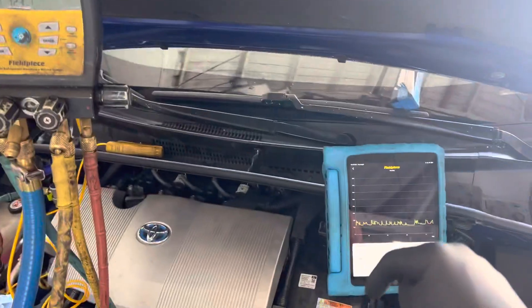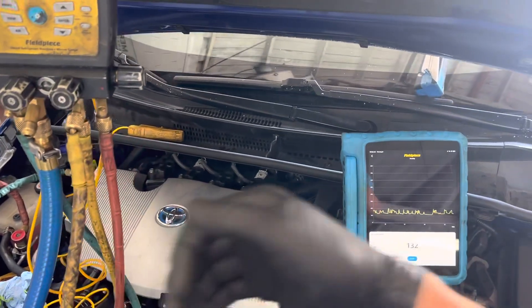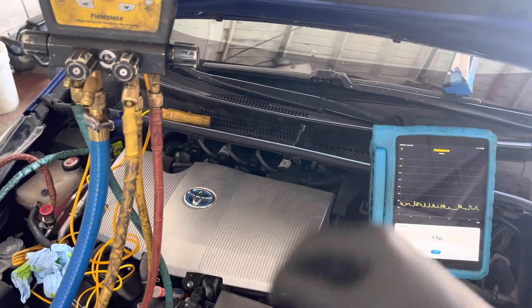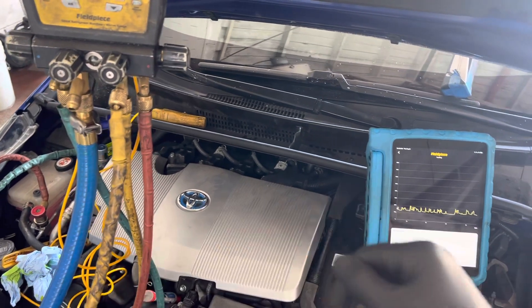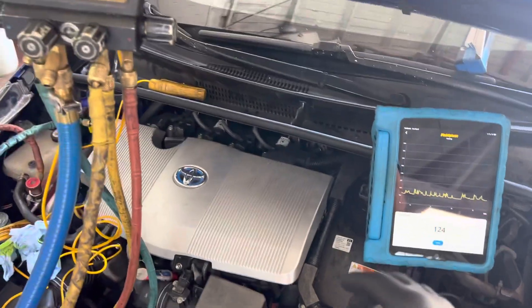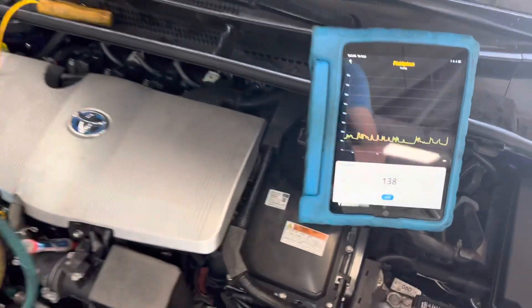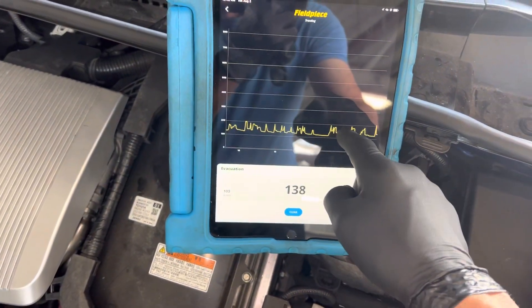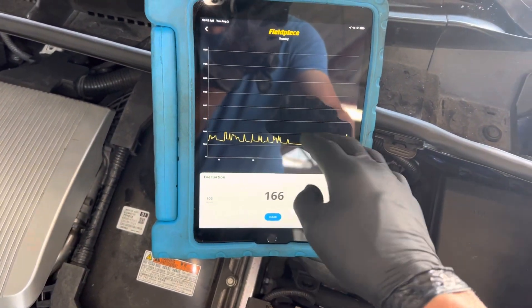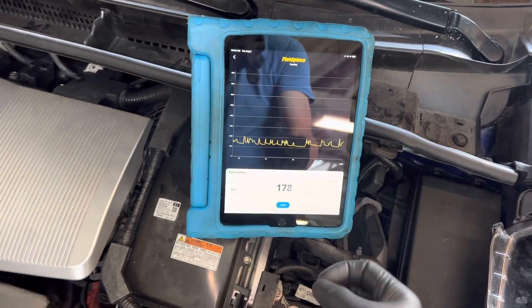And in this area of San Francisco it's been foggy. This is the time of year where fog starts rolling in, and on this part of San Francisco it's like 95–99% humidity every day and every night when the fog rolls in. So the moisture content in the air was extremely high. These little peaks you see is moisture bubbling and boiling out of the oil and out of the pores of the metal.